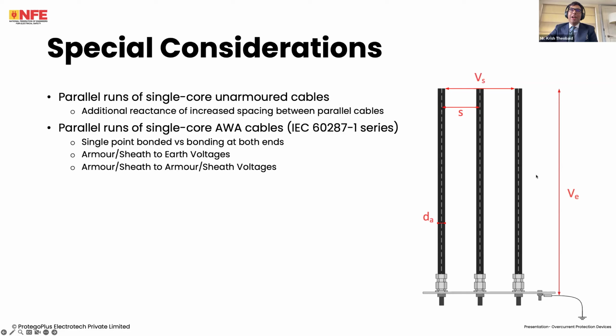If we're using aluminium wire armored cables, not only is this concern there, there is also the question of whether we connect the aluminium wire armor to earth, to the PE, at the load side, at the supply side, or at both sides. Single point bonded versus bonding at both ends. Then we have to consider what voltage is going to be induced in the sheath, and what about circulating currents induced in this sheath? Look, I'm not going to go into too much detail about this. You can look at the 60287-1 series, and there is information also in certain guidance documents. If you have questions about this, you can take them separately. I had prepared a bunch of slides, but if you dig into this, it is really a can of worms that we are opening here.